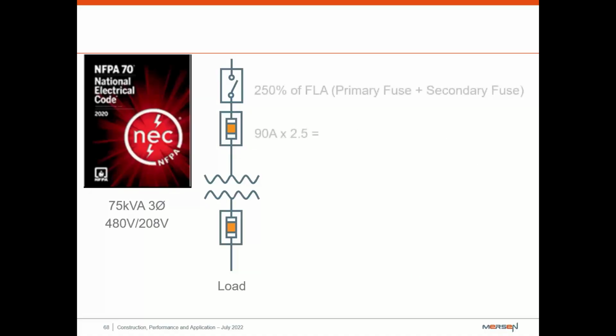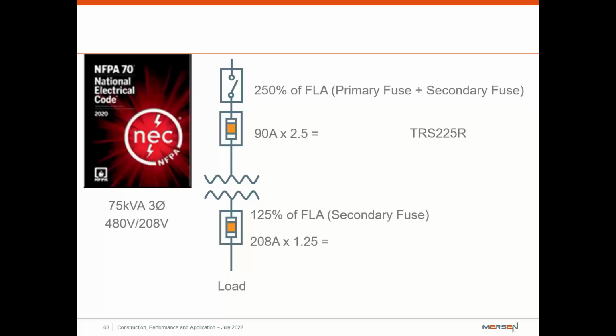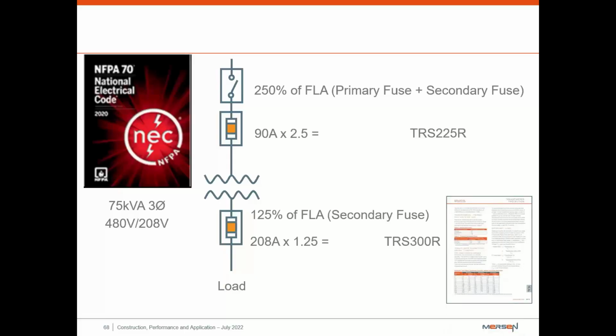So getting into primary and secondary fusing. This is where you're going to want to do 250% of the full load for primary and secondary. So for the primary, you're going to have your 90 amps at 250%. It's going to be the TRS 225. So the secondary, you can have 125% of the full load. So you have your 208, which will be 260 amps. So you go to the next size up, that'll be the TRS 300R. And again, the literature is going to be available online. We're not going to expect you to calculate all this stuff.